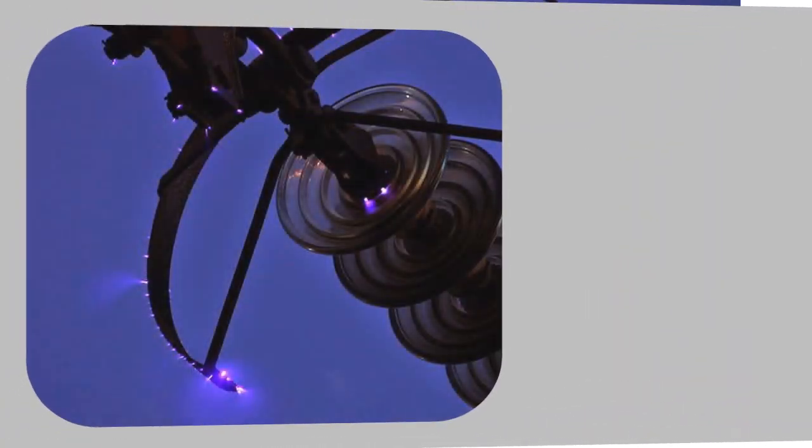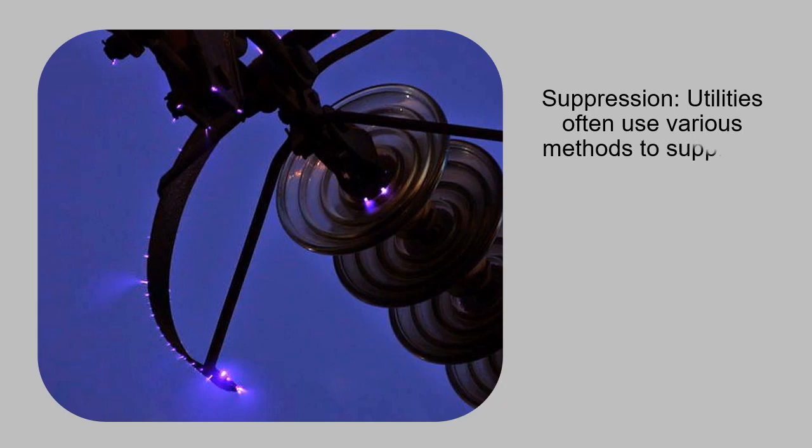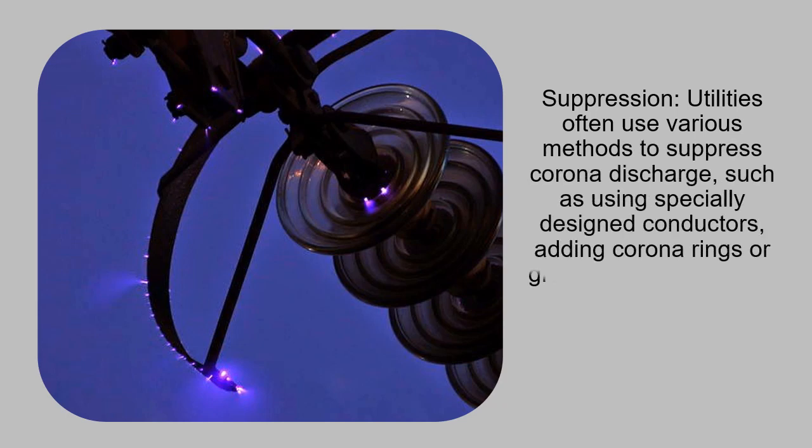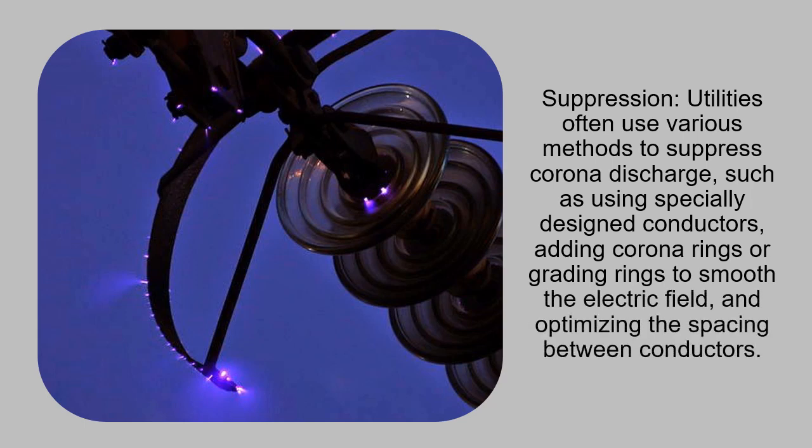Suppression: Utilities often use various methods to suppress corona discharge, such as using specially designed conductors, adding corona rings or grading rings to smooth the electric field, and optimizing the spacing between conductors.